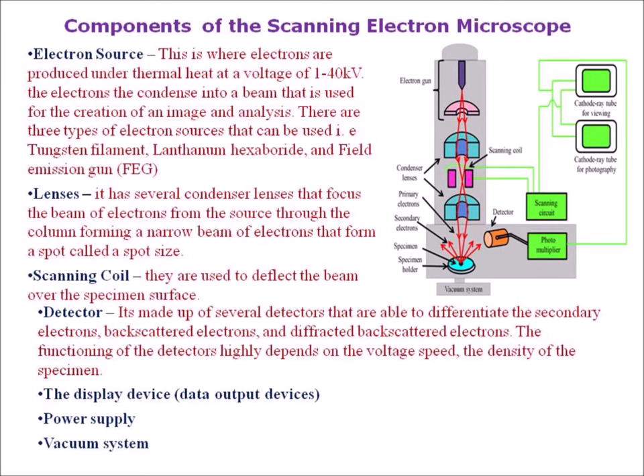Here we can see the components or parts of a scanning electron microscope. The electron source is there. In a light microscope we use a light beam, but here it is an electron source — tungsten filament, lanthanum hexaboride, and field emission gun. The lenses consist of several condenser lenses that focus the beam of electrons from the source through the column, forming a narrow beam of electrons that form a spot called a spot size.